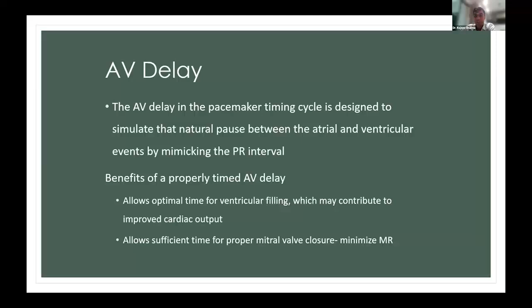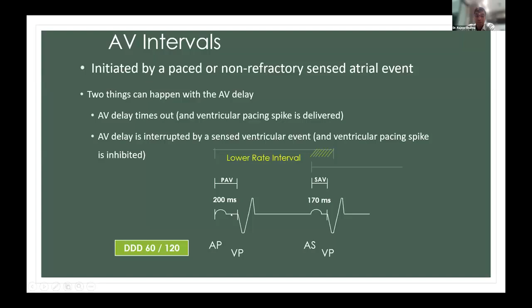So two things can happen after the AV delay. The AV delay times out, and then the ventricular pacing spike is delivered, and ventricular pacing will be there. If the AV delay is interrupted by a sensed ventricular event, then there will not be any ventricular spike, and there will be A sense and V sense, or A pace and V sense. As we can see here, it is atrial pacing followed by the paced AV interval, and after that ventricular pacing is there. Similarly, after the sensed event, there is the sensed AV interval and ventricular pacing. If in between any ventricular impulse comes, then it will be sensed and there will not be any ventricular paced events.